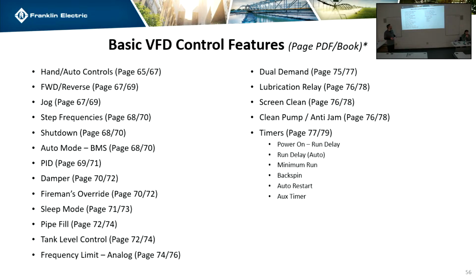I don't think we use it for anything, but if you guys have just a drive where you're building a panel, you could also do the same thing where you have an input tied to Fireman's override, and once that gets hit, the output closes and your bypass contactor gets pulled in.